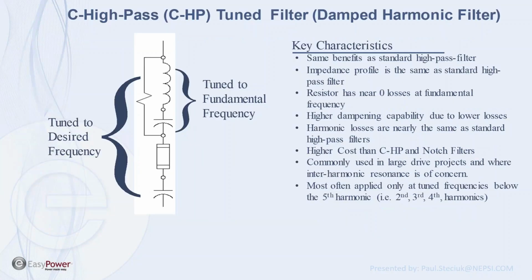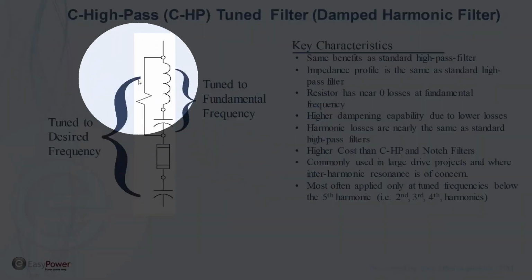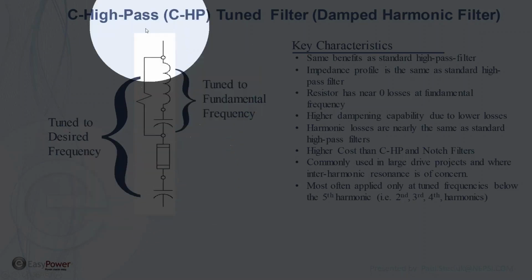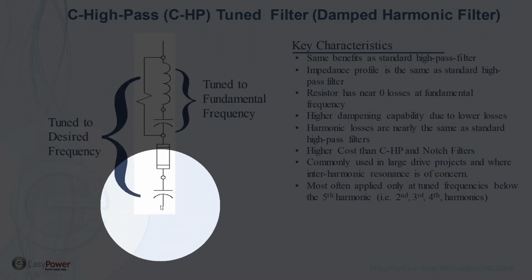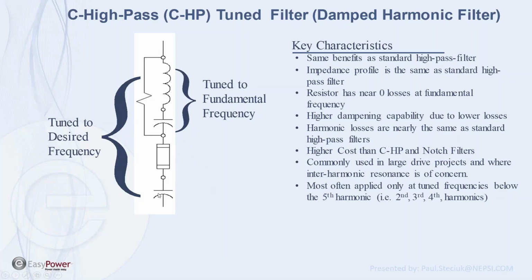One of those things to do is to think about a C high pass filter. If I had to decrease this value of resistance so far and my losses have gone up so much, a lot of those losses will be associated with 60 hertz losses, and a C high pass filter will eliminate that. The spreadsheet tool we have will give you the parameters for resistance for these parameters, including this value down here.